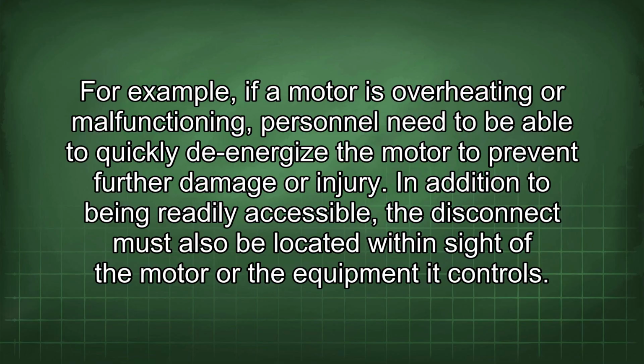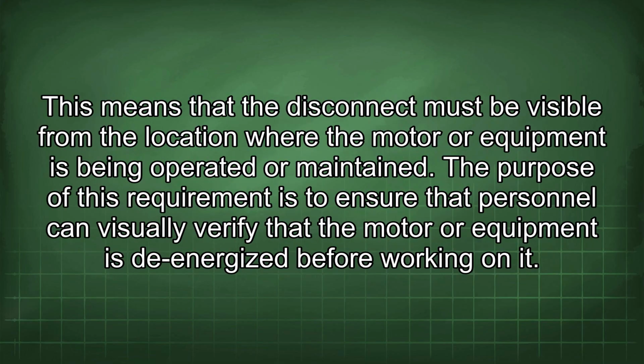In addition to being readily accessible, the disconnect must also be located within sight of the motor or the equipment it controls. This means that the disconnect must be visible from the location where the motor or equipment is being operated or maintained. The purpose of this requirement is to ensure that personnel can visually verify that the motor or equipment is de-energized before working on it.